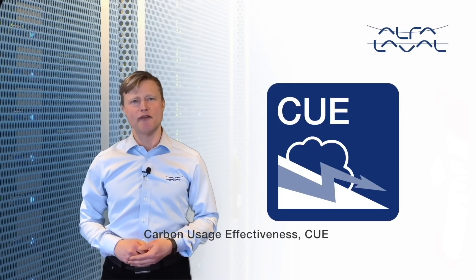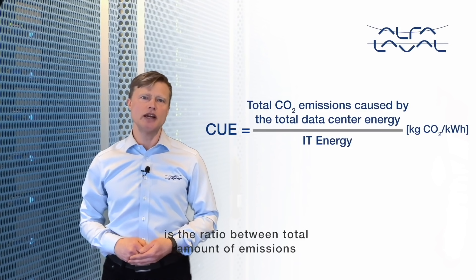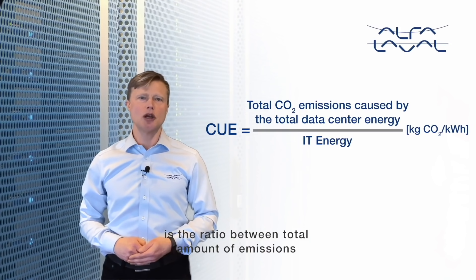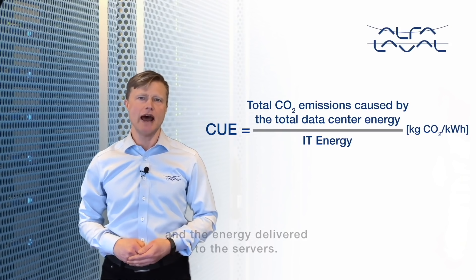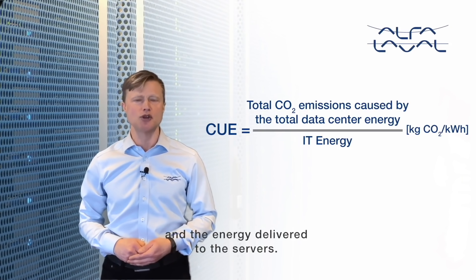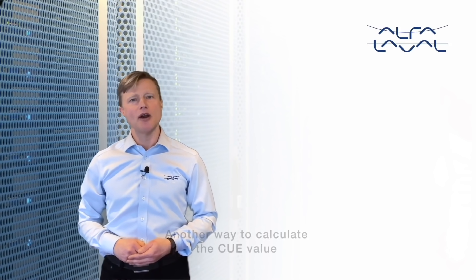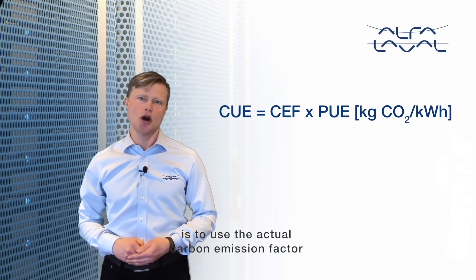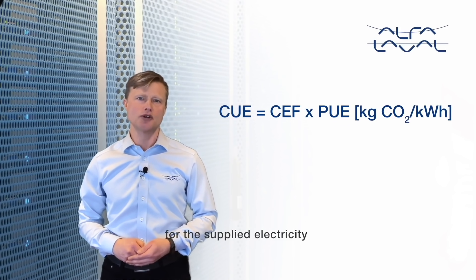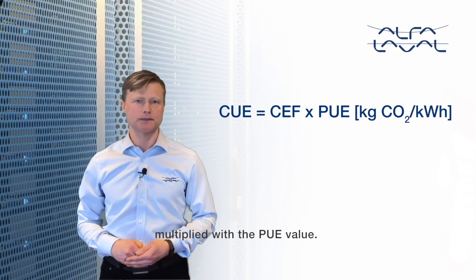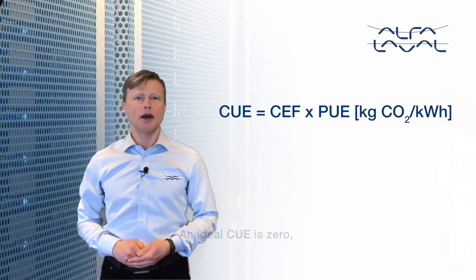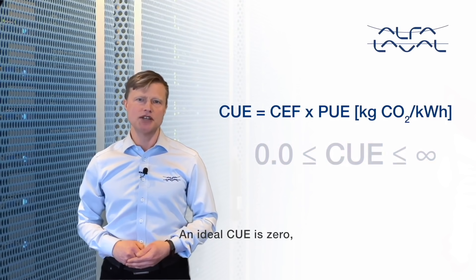Carbon Usage Effectiveness (CUE) is the ratio between the total amount of emissions caused by the total energy supplied to the data center and the energy delivered to the servers. Another way to calculate the CUE value is to use the actual carbon emission factor for the supplied electricity multiplied by the PUE value.